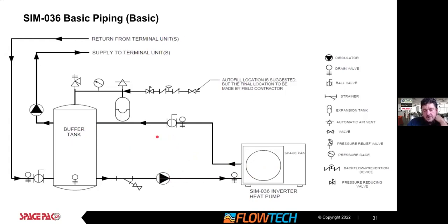Buffer tanks are real important. I'll just touch on it here. Buffer tanks on SpacePak systems do 2 things. They provide some system volume, but the real benefit, which is critical to efficient operation, is that it decouples the flow rate from the system, whether it's radiant floor or high walls, thin walls, air handlers. It decouples the needed flow rate for the system and the needed flow rate for the SpacePak. This 3-ton SpacePak requires 7 GPM.